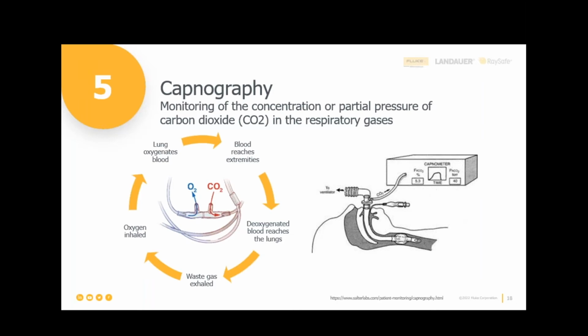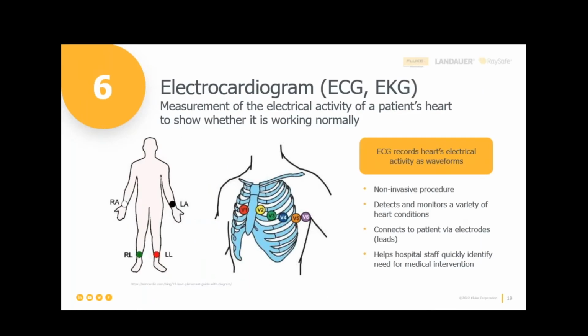The difficulty here is that the apnea monitor built into, especially the end-tidal CO2 parts of the patient monitor, needs to see a breath rate, a repeatable breath rate that makes sense. So the cylinder usually has a valve on top, and you're pressing the valve as repeatably as you can. And sometimes you're going to trip that apnea monitor because it doesn't look right to the assessment based on the algorithm in that particular part of the device. But you're going to use a certified test gas.